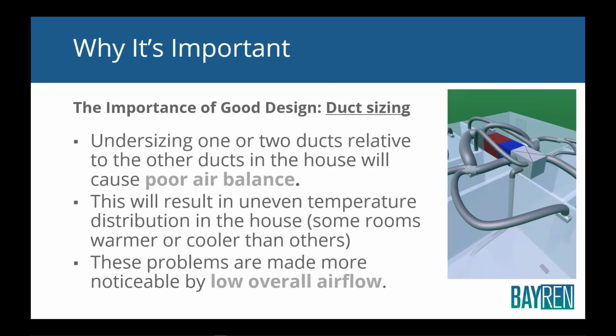Undersizing one or two ducts relative to the other will result in poor air balance. And that's what most comfort complaints are: oh, the baby's room is always hot, or the upstairs is always hot and the downstairs is always cold. All of those have little or nothing to do with equipment sizing. Oversizing will make those issues worse, but those are poor air balance. And that's where good duct design comes into play, okay?